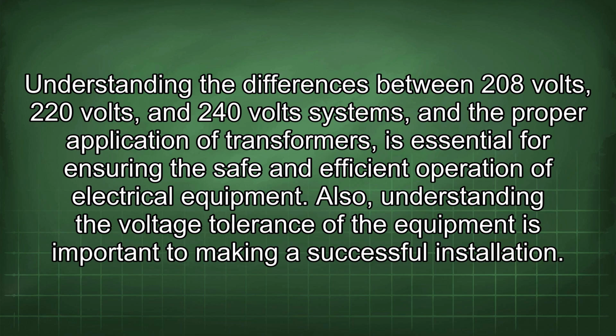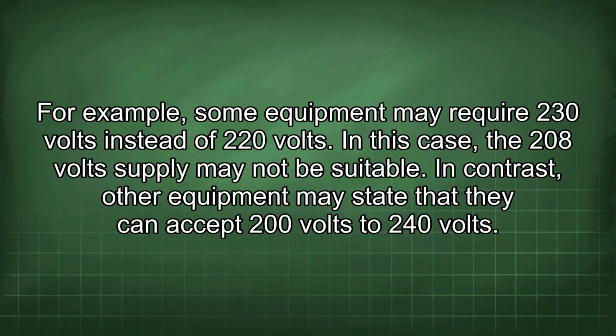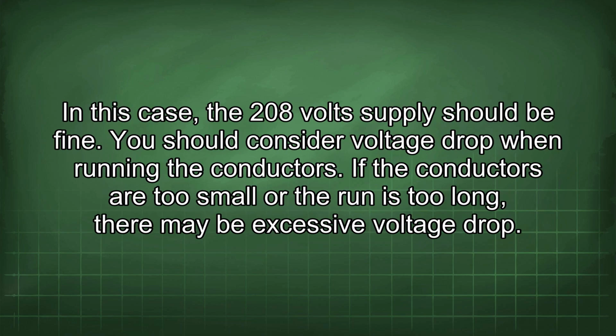Understanding the differences between 208 volts, 220 volts, and 240 volt systems, and the proper application of transformers is essential for ensuring the safe and efficient operation of electrical equipment. Also, understanding the voltage tolerance of the equipment is important to making a successful installation. For example, some equipment may require 230 volts instead of 220 volts. In this case, the 208 volt supply may not be suitable. In contrast, other equipment may state that they can accept 200 volts to 240 volts. In this case, the 208 volt supply should be fine.